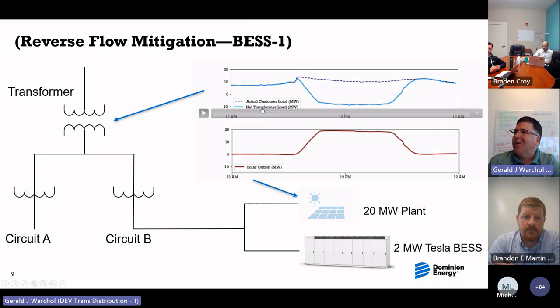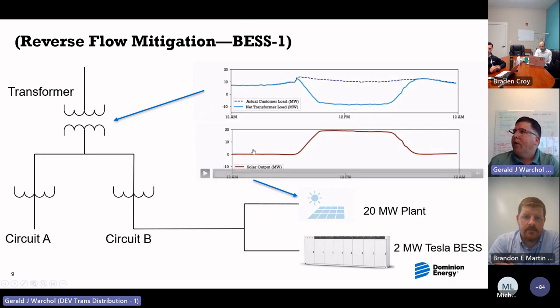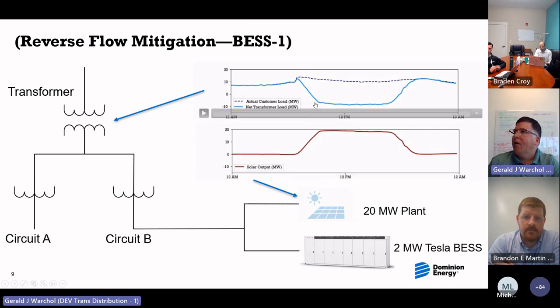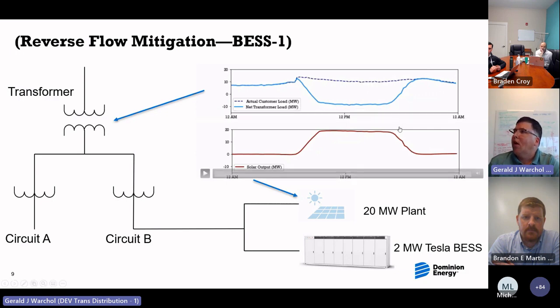Basically what happens is when the solar comes online, this lower graph shows the load on the transformer drops down. It actually reverses and goes negative, it starts backflowing out onto the system. But then as soon as the solar starts coming offline, all of that load comes racing back onto the bulk electric system. So all of the generators primarily tied to the bulk electric system have to play catch up and make sure that generation and load is balanced. So the more penetration you get, the more prevalent this problem becomes.